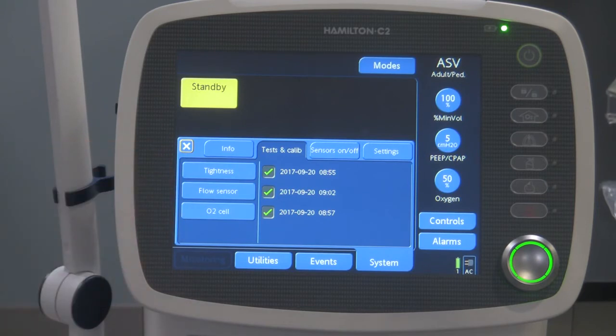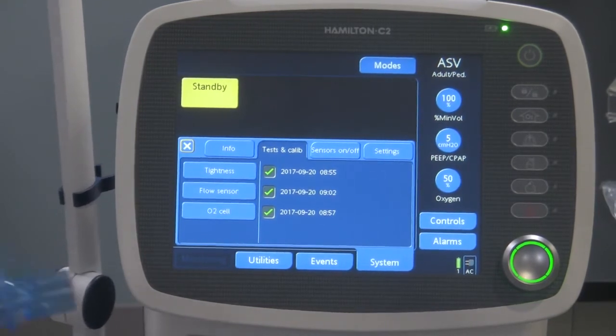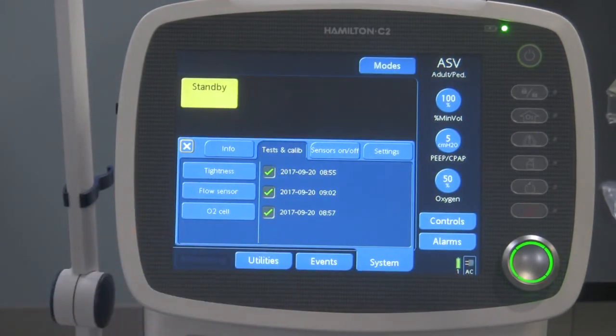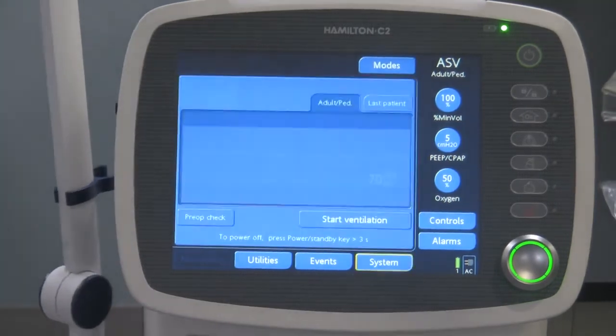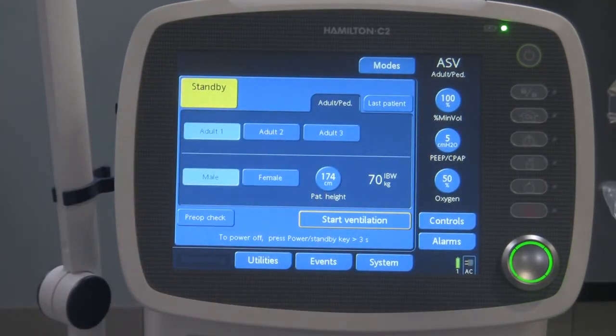So all these tests are identical to the Hamilton G5 ventilator self-test. So if you have done the self-test on the G5, or if you've watched that video that I made on how to do the self-test on the G5, you'll find doing the self-test on the C2 very, very similar. And with this flow transducer though, you have to make sure that when you turn the flow transducer for that flow sensor test, that you use that adapter that I showed you that's in the packaging. And that's in essence how you start up the ventilator and access the self or pre-use check. I'm not going to do the pre-use check because it is so similar to the Hamilton G5. Again, before you do the test, make sure all your connections are nice and tight.